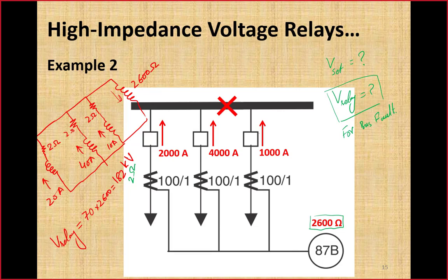That is too high voltage across the relay in case of an internal fault, and that would not appear without damaging the insulation of the secondary circuit of CT secondaries. That's why some protection is required on the secondary side of CTs to avoid this much high voltage to build up. Next we are going to find out the V set.